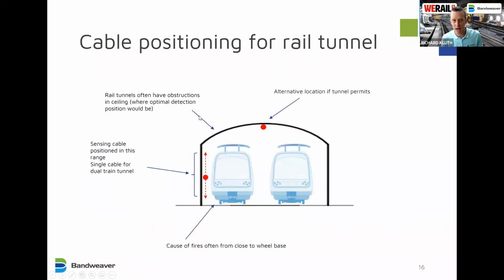And where do you put the cable? Well, in most linear heat detection applications, it's normally at the highest point of the room or the facility, because that's where the heat gathers and is the hottest. For railed applications, this is not always the case, as there's potentially overhead cables in the way, and also fires quite often initiate around the wheelbase. So the preference tends to be on the wall, but this is always decided in conjunction with the client.